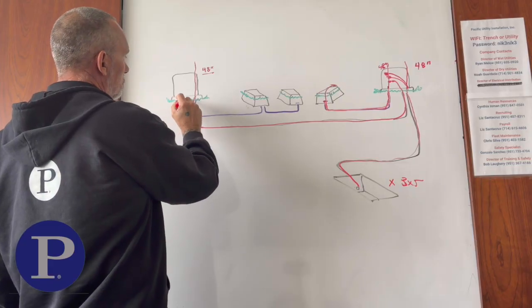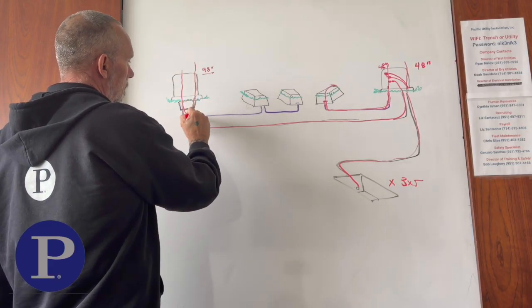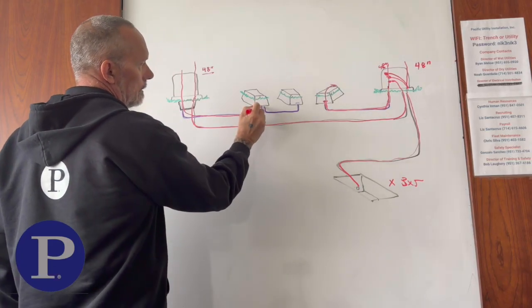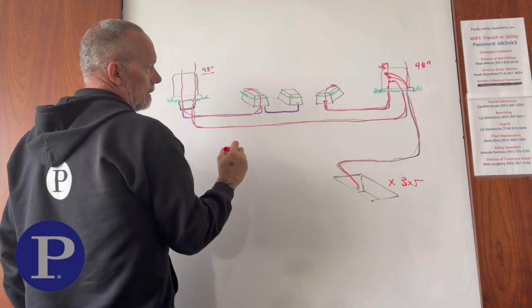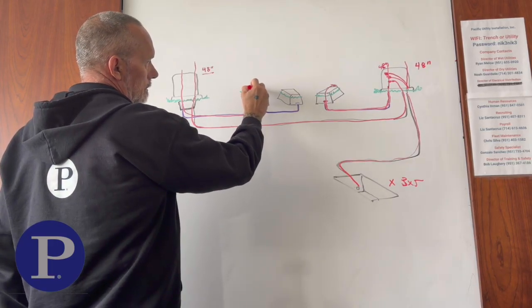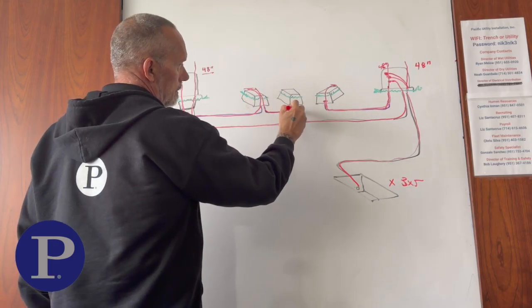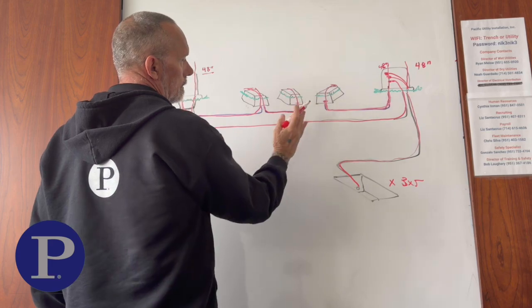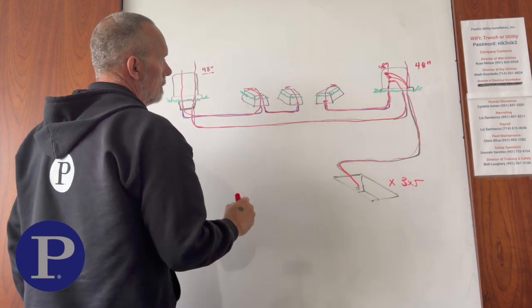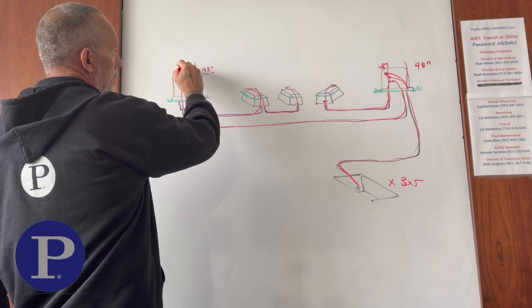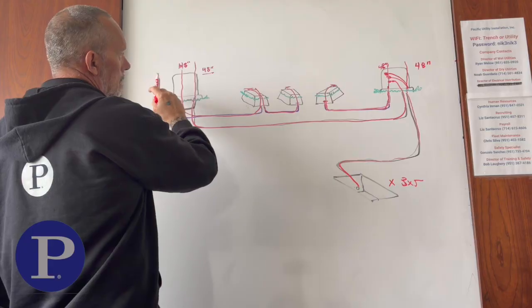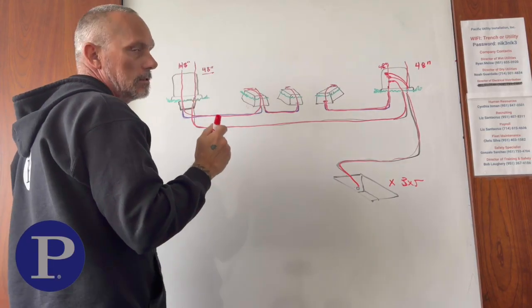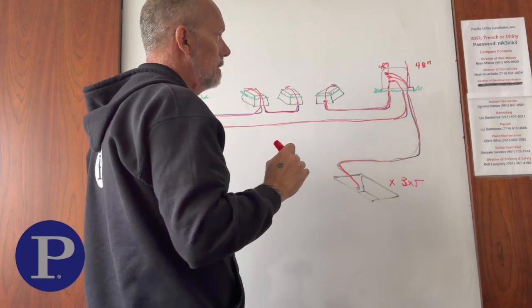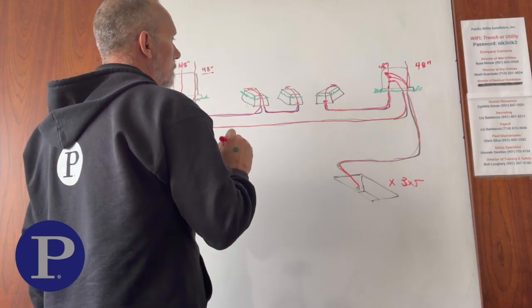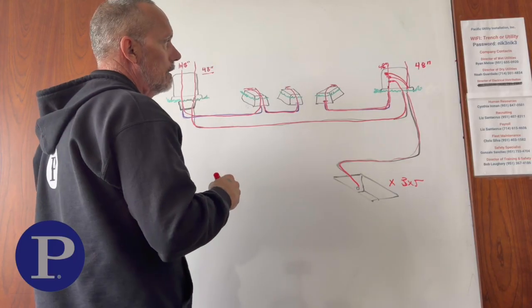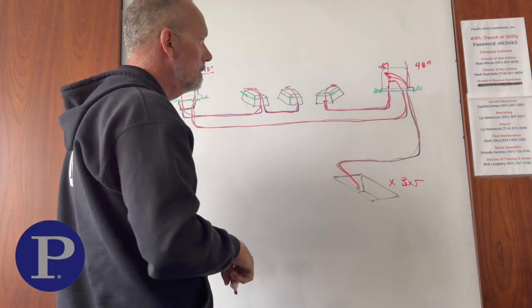This transformer over here, I'm going to feed it in here. We're going to come up into this handhole. Again, we're going to pull it, lay it over, cut it to the edge of the handhole, and then this other secondary cable, when we feed in, it's going to daisy chain into this handhole. Same thing, you're going to pull it up, arch it over, and cut it to the other side of the handhole. This also you want 48 inches above where you're going to cut it. If you ever have any questions about where to cut it, you want to get with your foreman and make sure that you're not cutting it too short. Cable that's cut too short has to come out and then we have to re-pull it, all because it's a few inches short.